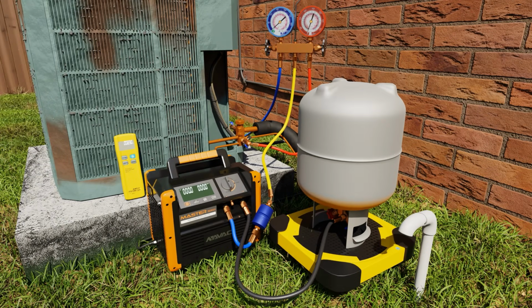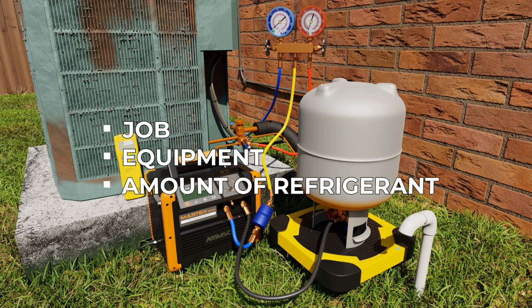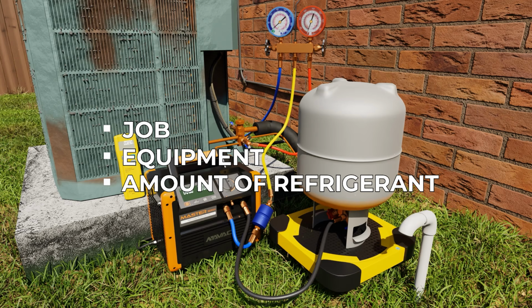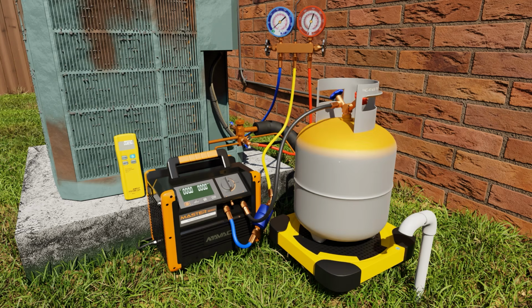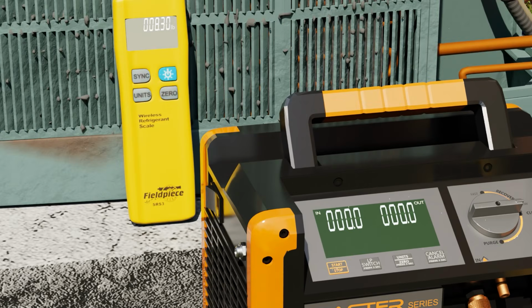At this point, you would want to note how much refrigerant you remove from the system to stay in compliance with EPA regulations. Also, tag the tank with the job, equipment, and amount of refrigerant put into the tank. This way, you can keep track of how much refrigerant is in your tank. You can now disconnect everything because the system is now empty of refrigerant.